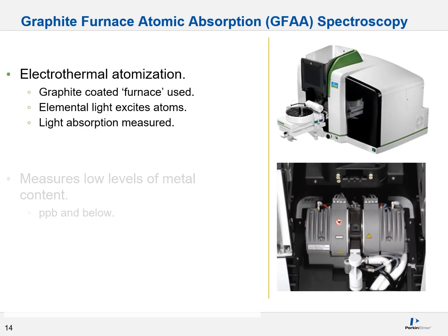Graphite furnace atomic absorption spectroscopy, or GFAA, is the brother to flame atomic absorption spectroscopy. This instrument relies upon electrothermal atomization. Instead of using a flame, it uses high voltages to generate a tremendous amount of heat and effectively atomize your sample. This is done in a graphite-coated furnace. Once your atoms are generated, elemental light is used to excite them, light absorption is measured, and back-calculated to determine the concentration of your metal. This technique measures low levels of metal content — parts per billion (ppb) and below — and relies upon extremely low sample volumes, in the microliter range.